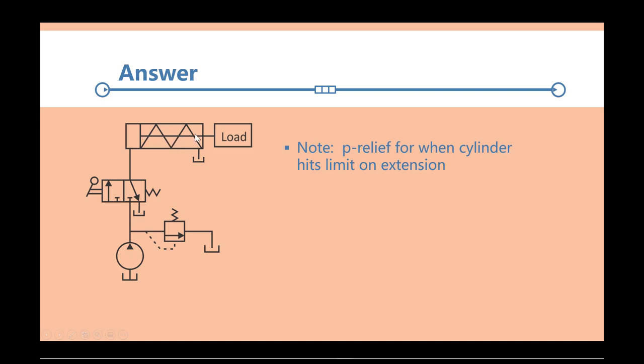But, of course, when the cylinder retracts, when the spring acts, what has to happen is that the fluid in the cap end has to have a place to go. And so we have provided that through this default envelope here, the one that is active when the valve is not actuated because of this spring here. And the fluid can flow back to tank, and the fluid from the pressure source is blocked, and it relieves through the pressure relief valve, the PRRV, into the tank.